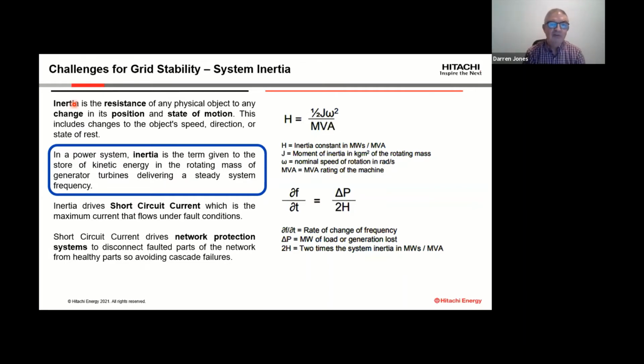So what we're experiencing is a fundamental shift in the way the system is going to be operated in the future. As I tried to say at the later points in the slide, inertia drives short circuit currents. The fact that we have that energy in the system, when there is a system event or some kind of network event or a fault, the inertia that's in the system continues to drive energy into the system. No matter what the network is actually doing, the inertia continues to drive energy into the system in the form of a short circuit current. And it's the short circuit current, this energy that's driven into the network in the event of a fault or a system event, that drives network protection systems, which disconnects the faulted part of the network from the healthy part again. So as I'm saying here, so avoiding system failures and avoiding cascade failures.